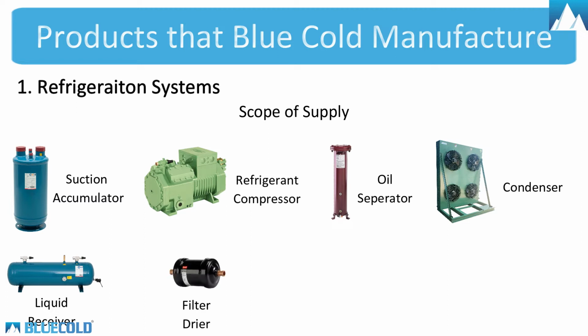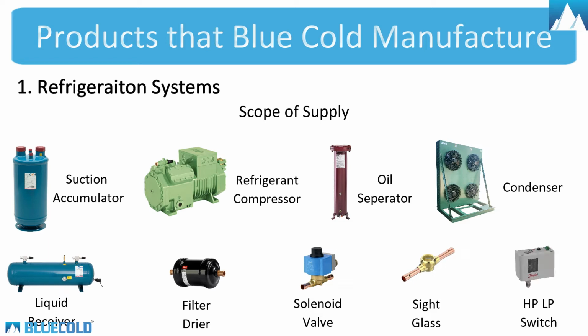Filter dryer. It filters the dirt or other particles present in refrigerant traveling in the system. Solenoid valve. It is an on-off valve to manage the pressure in the system and heat exchanger. Also, it can be used to block the flow of refrigerant at the time of servicing of the system to avoid refrigerant loss. Sight glass. It is to check the flow of refrigerant in liquid form from the system to the heat exchanger. HP or LP switch. It helps to sense the pressure level in the compressor.